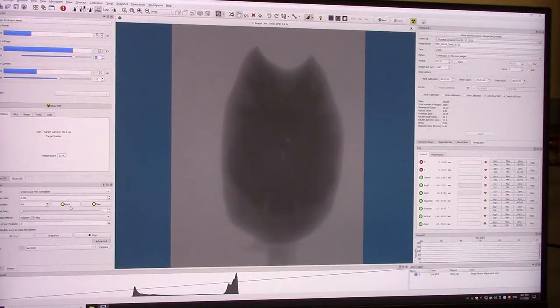Basically, it's going to shut off the X-ray source, and it's going to wait for the ghost image to be removed. And essentially, after a certain amount of time, it will then try to ensure that all the pixels have an equal amount of blackness, so to speak. And then there's also a gain calibration. That's the button right beside it. When you do a gain calibration, the first thing you're going to do is remove your sample from the field of vision. The gain calibration is to ensure every pixel has an equal amount of whiteness or brightness.